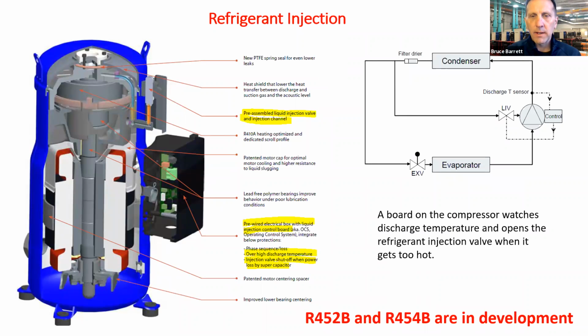Just another example showing the refrigerant line piping and how it controls that injection process. The compressor that we've chosen for R&D development, I highlighted in yellow a little bit. It has a pre-assembled liquid injection line right in the compressor. It's easy for us to do, manufacture, install, etc. It's all pre-wired. The compressor is monitoring its own discharge temperatures. It's got sensors all over the place on it. But it's really how to, Keith, I know you're a car guy. It's a turbocharger. We're not putting nitro in it, but we're putting liquid refrigerant in it to give it the gas it needs to do that heat of compression.